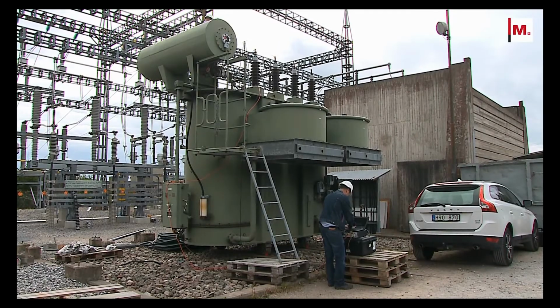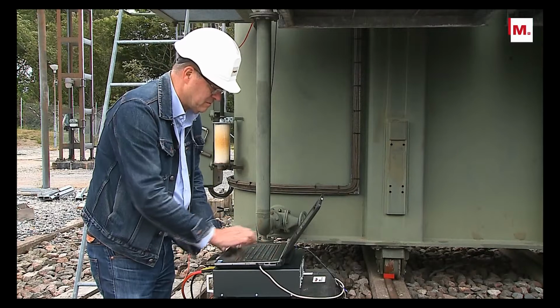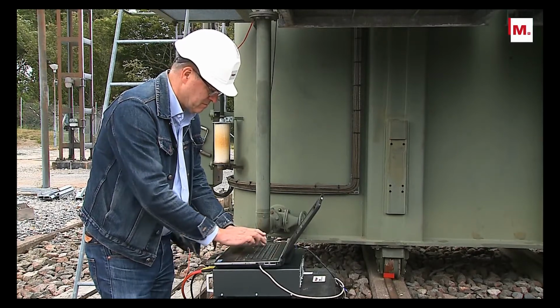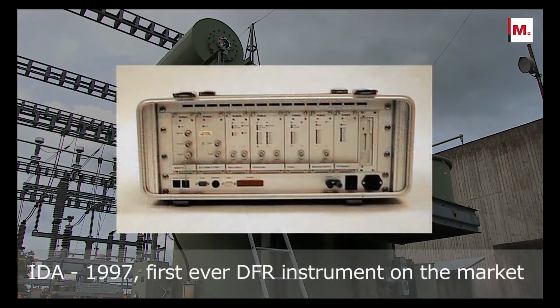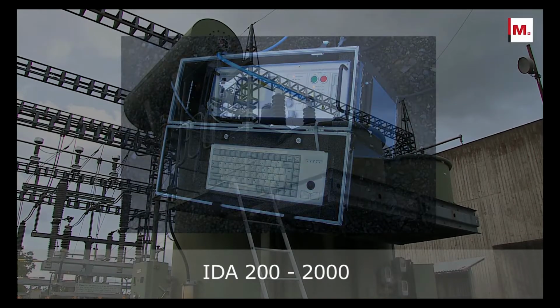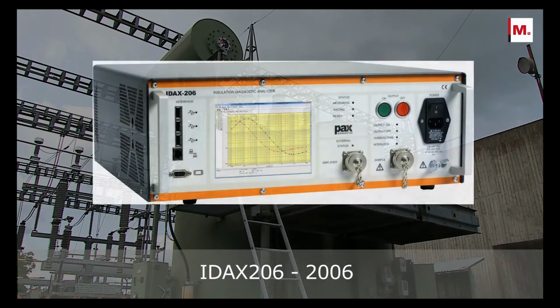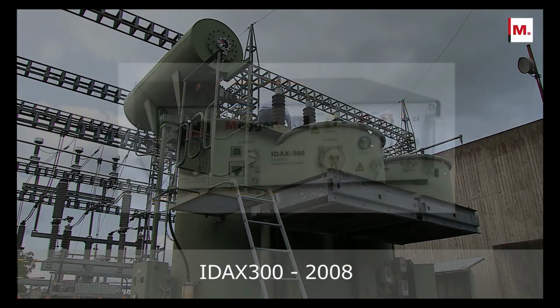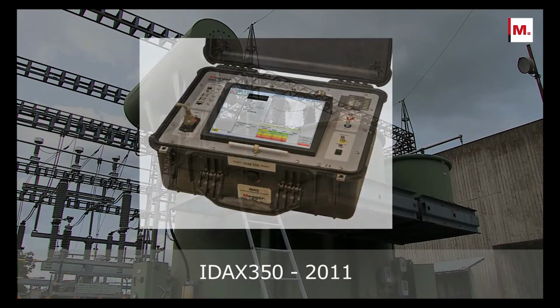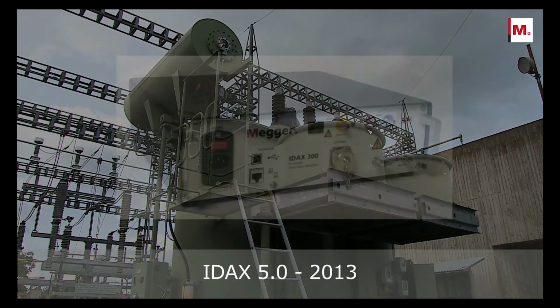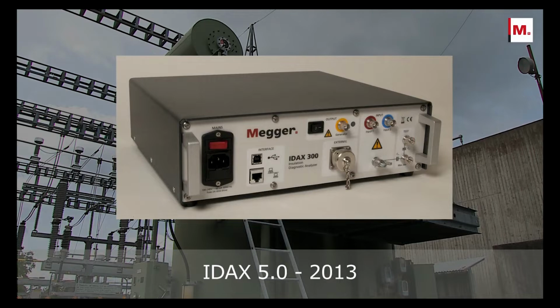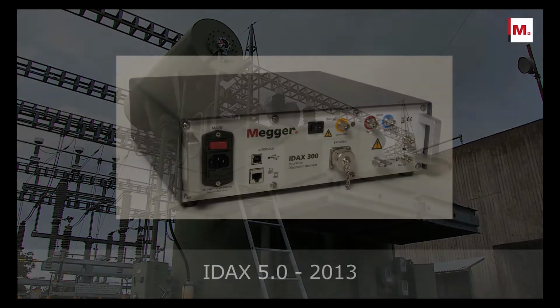Diagnosing the moisture content accurately in a power transformer is a very important tool in condition-based maintenance. The first IDAX model was released in 1997 and was the first test set for performing DFR testing in the field. Since then, IDAX instruments and the DFR methodology have been used by numerous customers globally. The methodology and technique have been refined over the years, and the 5th generation IDAX is the most versatile DFR instrument on the market. Fast, easy to use, and provides automated insulation analysis.